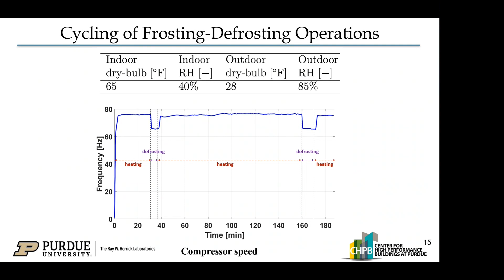This is the result where we compare the discharge and suction pressures. We can see that for discharge pressure, when you switch to the defrost cycle, there's a very fast pressure equalization process because the expansion valve is fully open. And when the system is operating in the second heating cycle, which spans 2 hours, we can see that after about 100 minutes, we observe a system performance degradation because discharge pressure is decreasing. You lose heating capacity to the indoor environment. This is because we lost heat transfer in the outdoor environment.